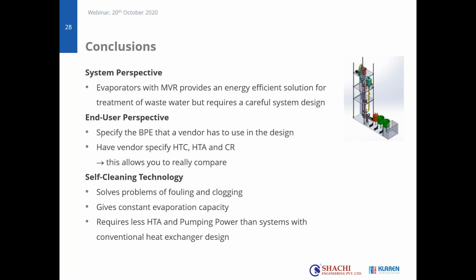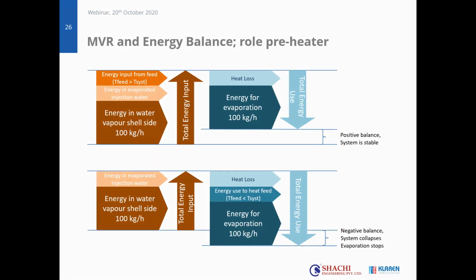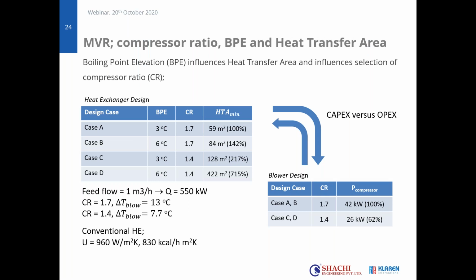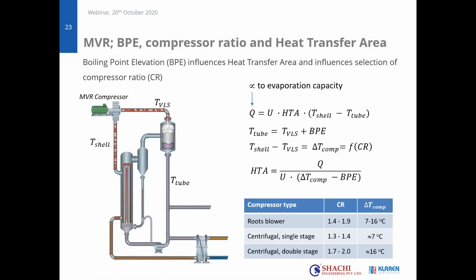I will go to the questions that have been raised. I think some of them I have already answered in the webinar, because I get a question about the compressor ratios. If I just click through, you see here the typical compressor ratio for the roots blower and also for the centrifugal compressors. That ranges from 1.4 for a single stage to 2 for a double stage. And for the roots blower, it has a wider variety, just because of how this roots blower is designed.